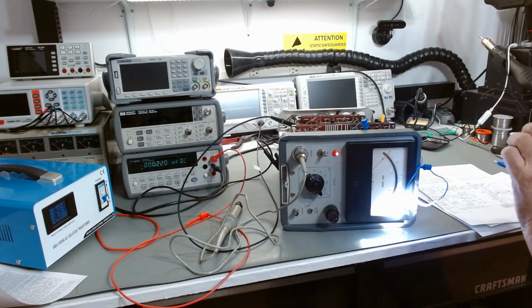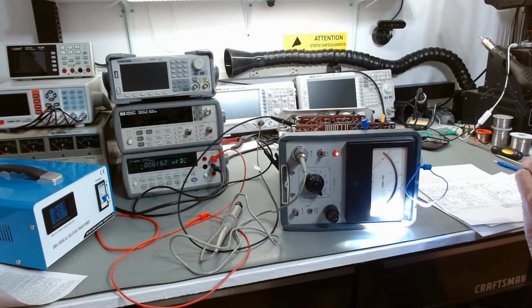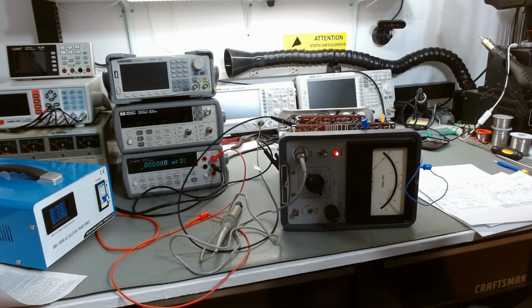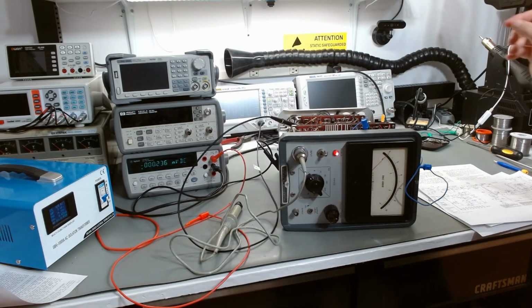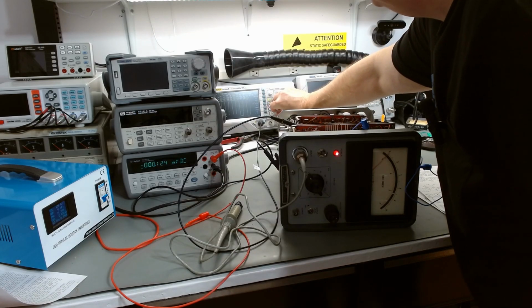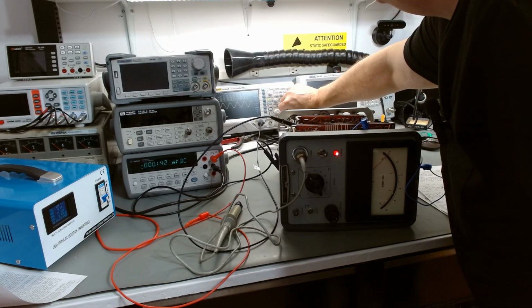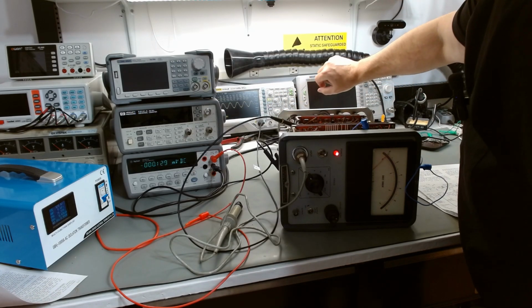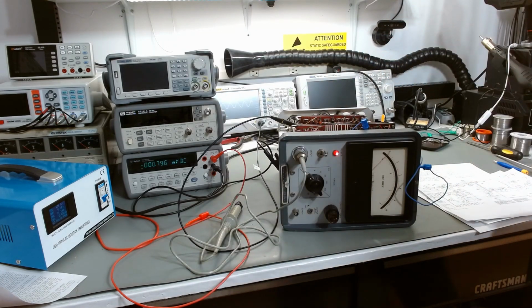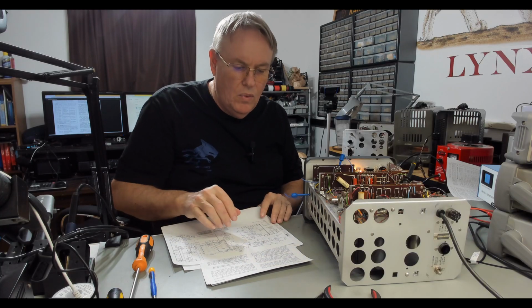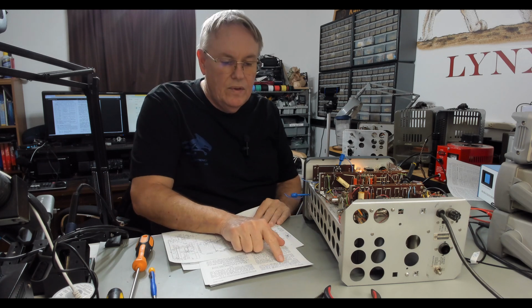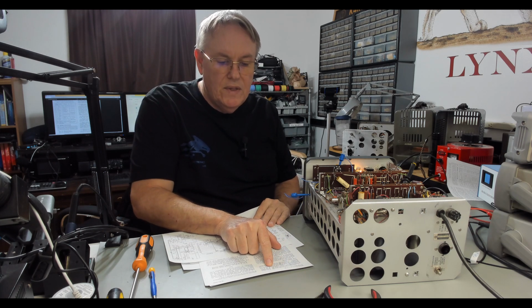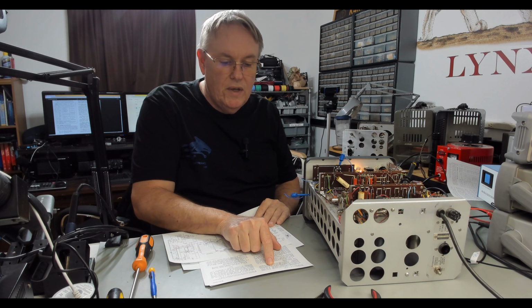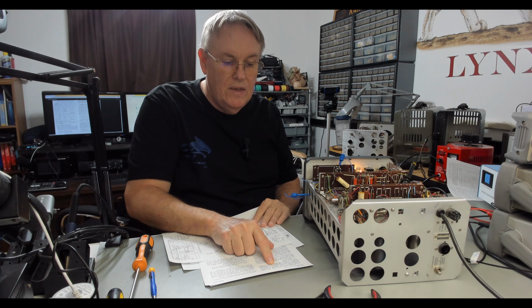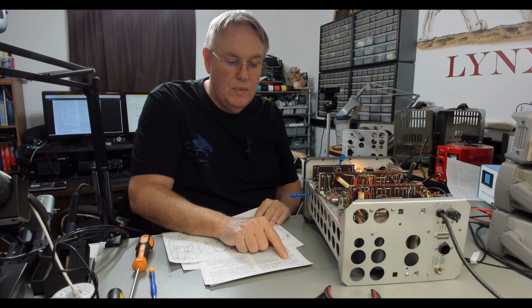Nothing yet. Oh, bouncing around. There we go. We're getting a signal now. So yeah, we've got a lot more signal there. Let me get it adjusted where I can see. We're getting 20 volts peak to peak, perfect sine wave. So we're getting a little more than what they're asking for. If the signal at test point 2 is not correct, check V7. If the signal at test point 2 is correct, check V8. If V8 is replaced, perform step 16 through 19 of the adjustment procedures.